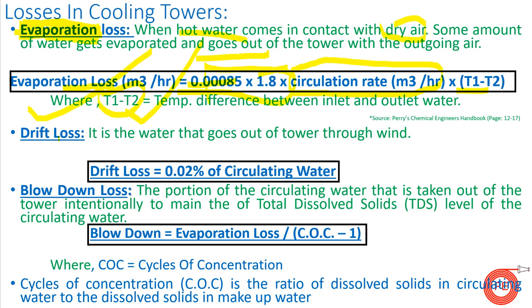For example, if inlet water is at 45°C and outlet at 35°C, then T1 − T2 = 10. The circulation rate is the total flow through the cooling tower. Multiplying all these values gives the evaporation loss. The next loss is drift loss — water that exits the tower carried by wind. As water splashes into small droplets, fast-moving air carries some outside through the louvers. Drift loss is calculated as 0.02% of circulating water.